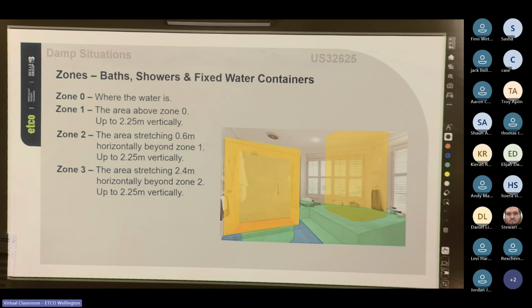So do you think, so in the picture, the orange surface on the shower or on the surface of the water is zone 0. Zone 1 is the orange leading up to the ceiling. Zone 2 is the green area, and zone 3 is the blue. Now, if you give me a sec, the picture here in this slide, I think that paints a little bit better of a picture. So it's a bit easier for us to understand when we talk about zone 0, 1, 2, and 3.